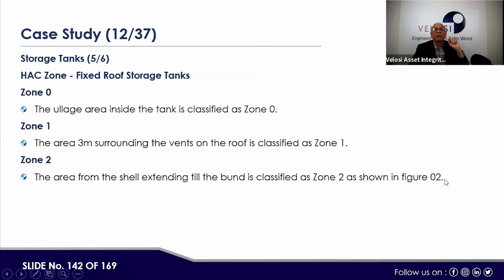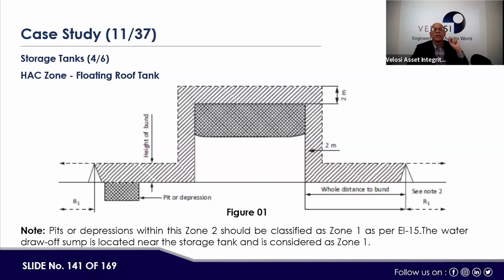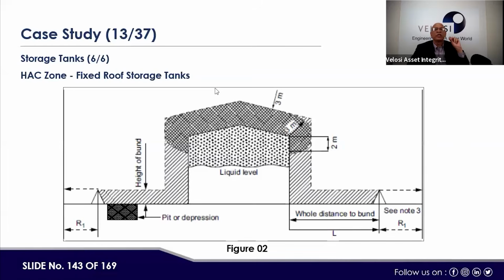If we go to the previous picture, this is an example picture taken from the standard. It's not actual, this is the standard. Here, this is zone 0 practically. It is a floating roof. Then this is zone 2 practically, and zone 1 is missing here, not applicable in this particular figure. So this is the other case, like fixed roof tanks where we have all three zones, zone 0, zone 1 and zone 2. Also, for example, it would be applied practically on the drawing on the other side.